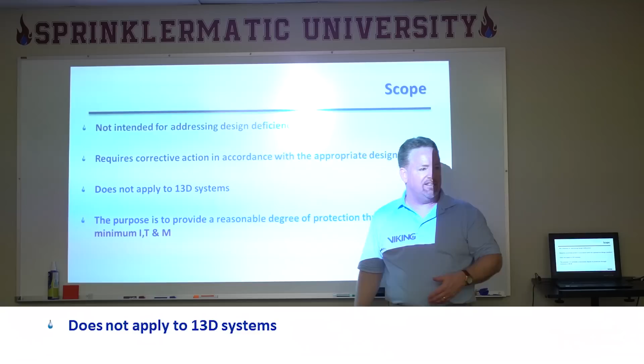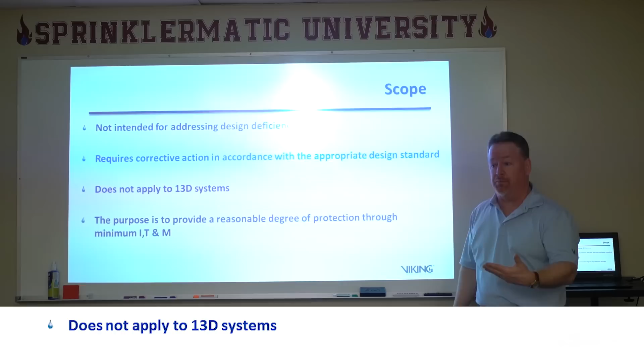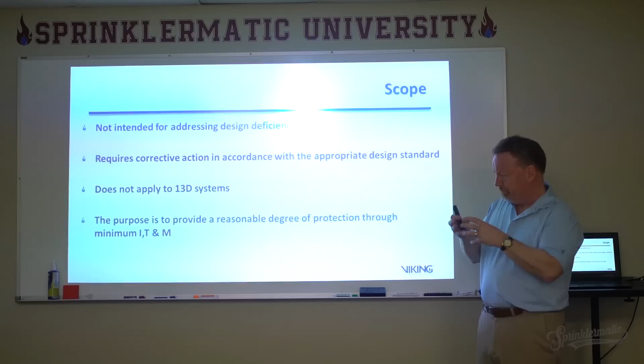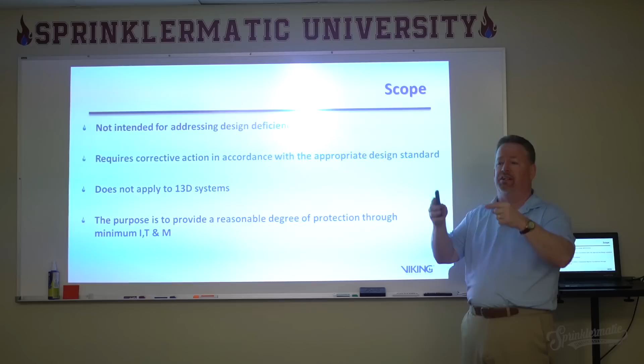It doesn't apply to 13D systems. Now, NFPA 13D is the standard for sprinkler systems in one- and two-family dwellings and modular, manufactured housing. So, small homes: NFPA 13D, one or two family dwellings. NFPA 25 does not apply to those sprinkler systems because they're private homes, you can't really get in and do an inspection. You can't mandate inspections on them. But NFPA 13D does have in its document a kind of proper care and feeding section for the system that you give to the owners, informing them of what is supposed to be done. It's still the owner's responsibility. It just has to be the homeowner.